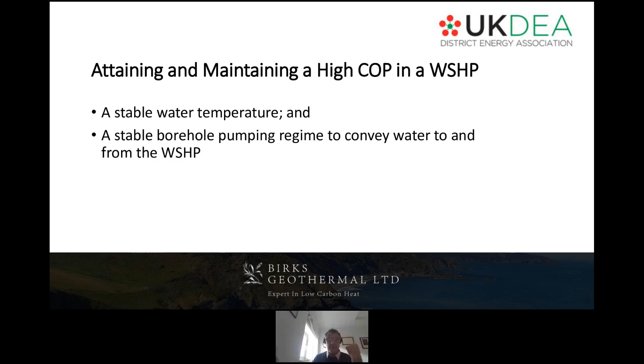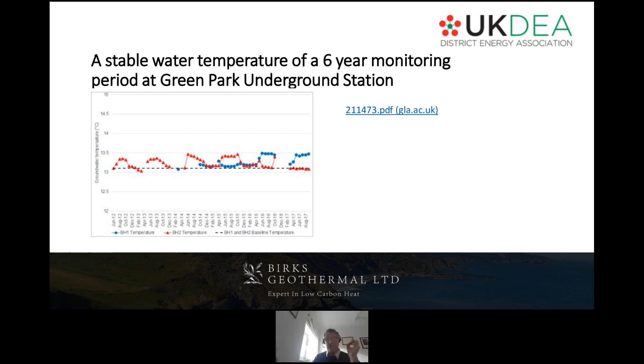This is actually from my PhD thesis, and it shows 6 years of monitoring of abstracted groundwater temperature at Green Park Underground Station. It shows that the temperature of groundwater was, despite some small, probably mini breakthroughs, stable throughout the year between 13 and 13.3 degrees. There's no rising or falling trend in the groundwater, and that's the kind of trend that for a district heat network we have to aspire to. So that's the temperature issue.